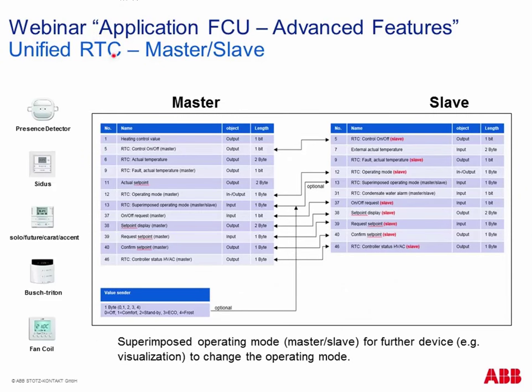To set up master-slave, you activate one device as master and the other as slave in the parameters. Dedicated group objects then become available — for example, 'RTC control on/off master' appears on the master side and the same appears on the slave side. You assign them the same group address and they work together. You do the same for all other group objects where you want information exchange. An optional 'superimposed operating mode' object is also available — a one-byte communication object with values off, comfort, standby, eco, frost — so a superior visualization can also change the operating mode, and both master and slave will respond accordingly.